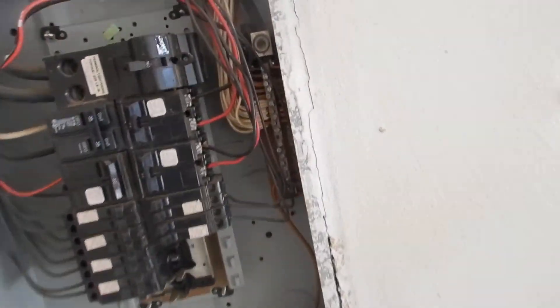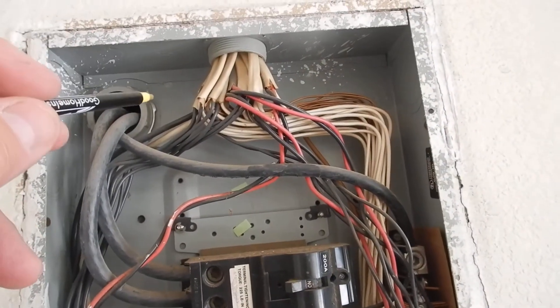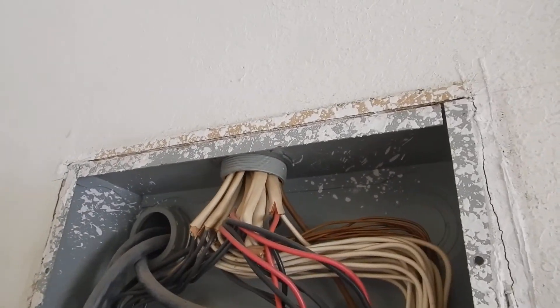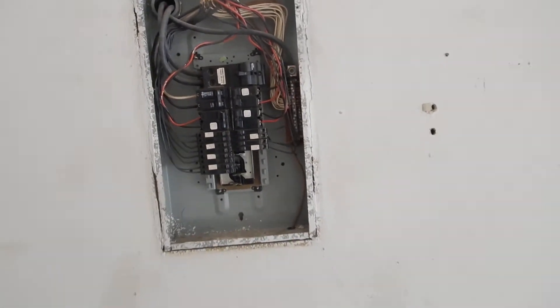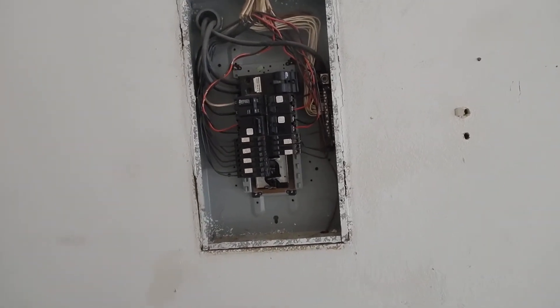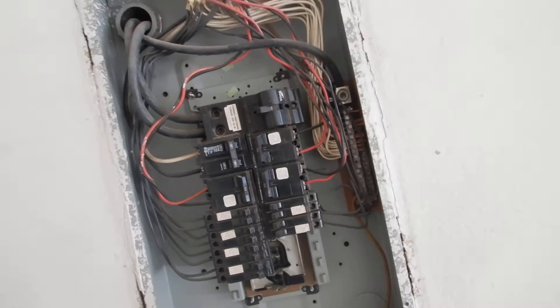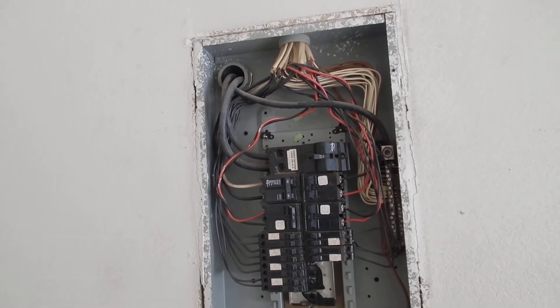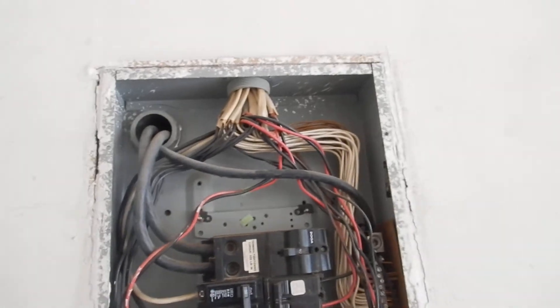The double-lug neutrals and grounds are more important. I'm not dissuading you from seeking perfection, but bundling is a very common issue and would be expensive to fix for a relatively small benefit. This house isn't going to change in selling price because someone discovers there's no bundling issue fixed — that just doesn't happen.